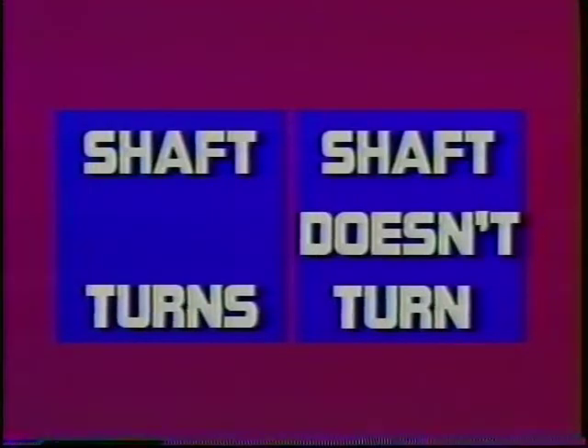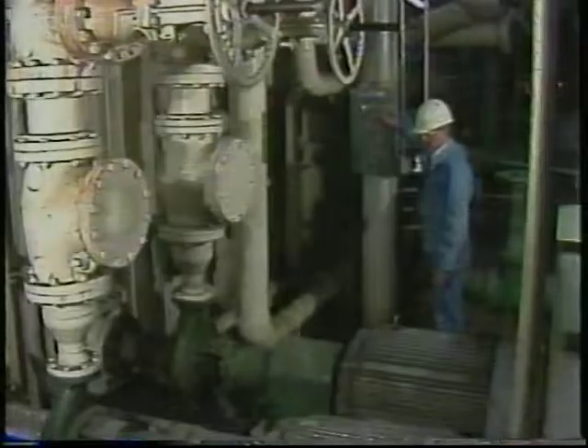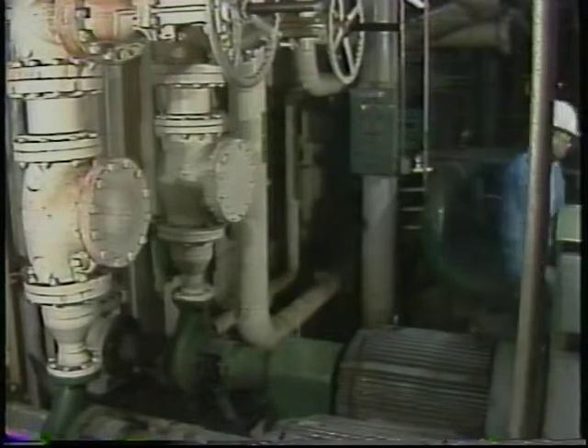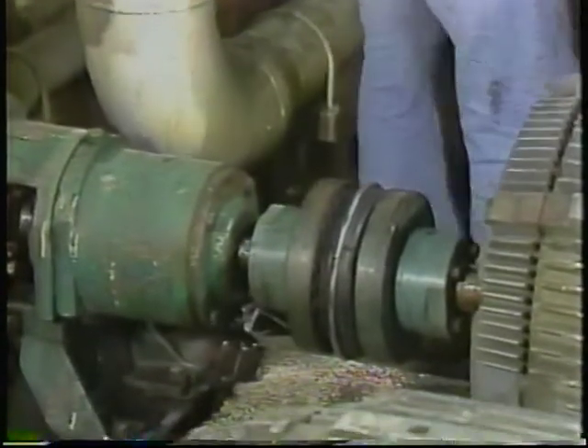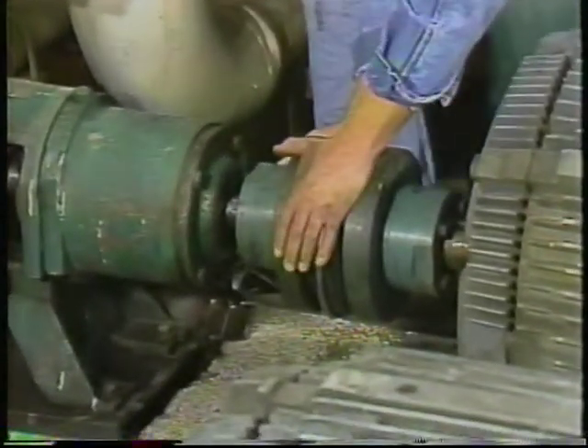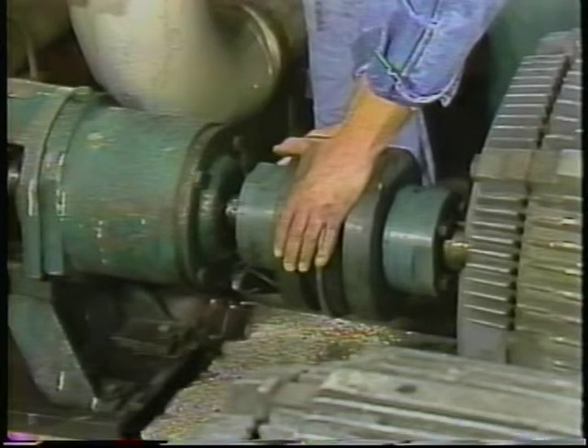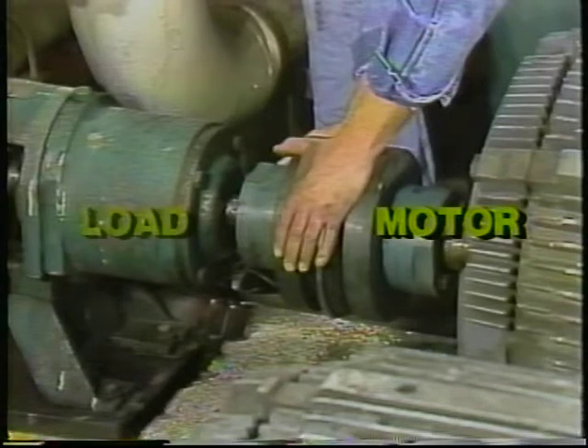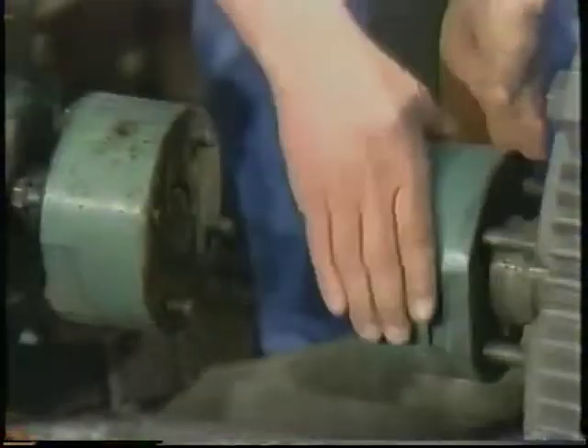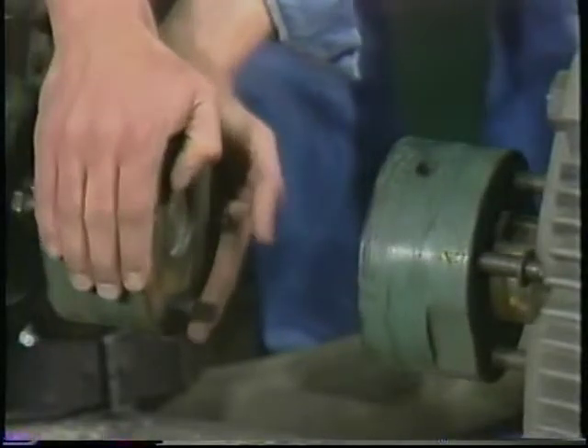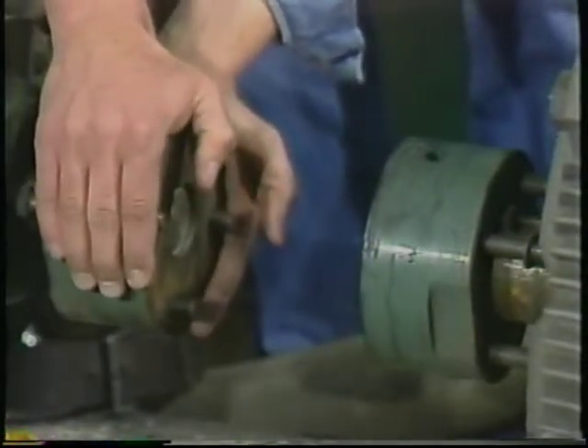Now, in the case when the shaft does not turn at all and the overload breaker trips quickly, you can assume that the overloads themselves are all right. Again, there are several probable causes. One obvious probable cause is that the shaft is locked up mechanically. The test is usually easy. Will the shaft turn? If it will not, subdivide the probable cause. The jam-up is either in the motor or in the load. Uncouple them and try to turn the motor and the load individually to see which is locked.